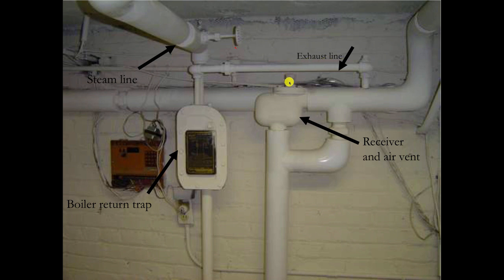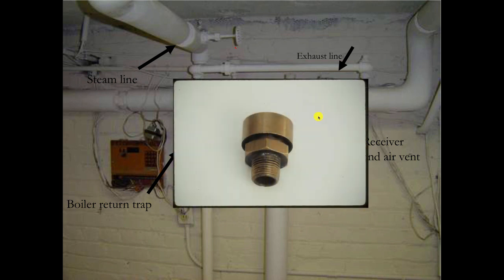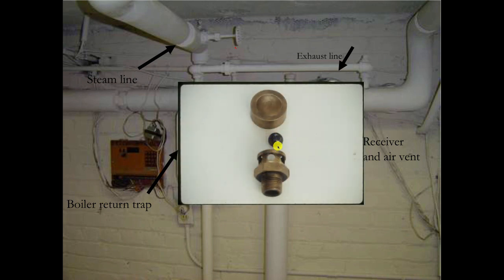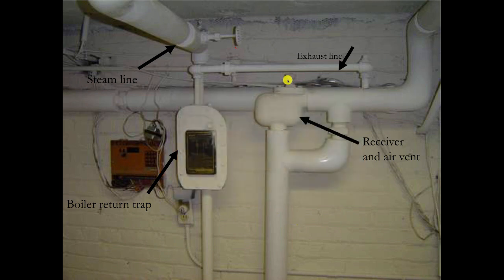This is the air vent for the whole building — this little thing here. Very, very small, very easy to miss, but essential. It's a three-quarter inch tapping, and if you remove the cap what you see in there is a ball. That ball was designed to produce vacuum in the days when we were burning coal. As the steam pushed the air ahead of itself, it would make the ball pop up, the ball would seat, and then when the steam condensed you'd get vacuum. So unless you're burning coal, I would remove that ball. Get a needle-nose pliers, just unscrew the top, take the ball out, put the cap back on — add it to your collection. Now it can't make vacuum.